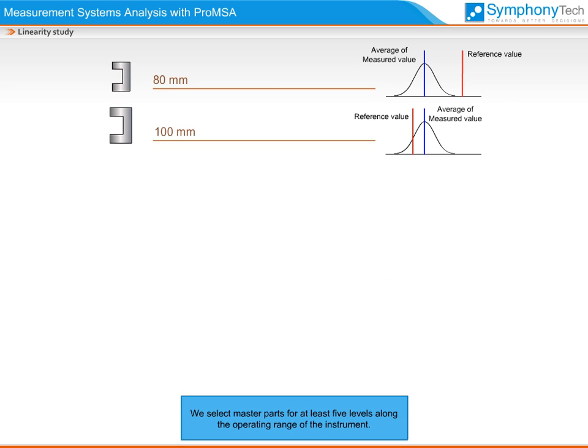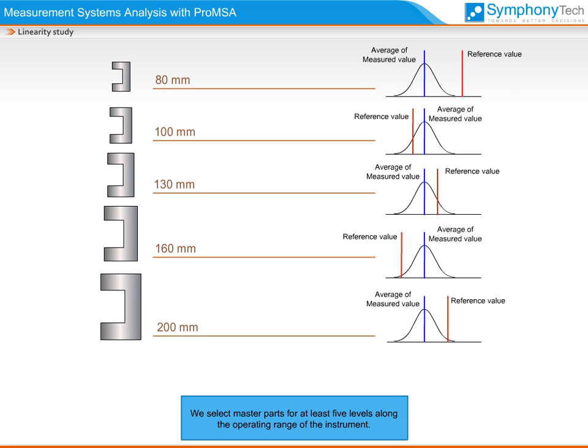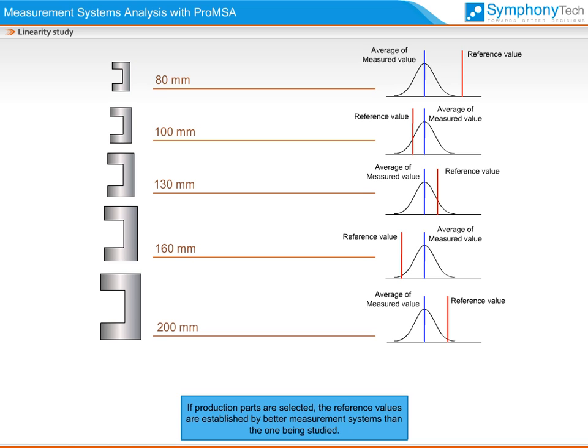We select master parts for at least 5 levels along the operating range of the instrument. We establish the reference values of the parts by traceable standard measures. The references can either be masters or parts selected from our production line. If production parts are selected, the reference values are established by better measurement systems than the one being studied.